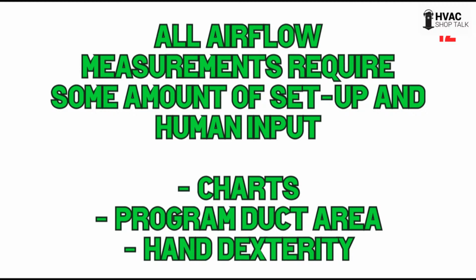Program duct area: all these devices like vane and hot wire, you have to put in what kind of duct you have if you want to calculate the CFM. You don't want to put in the wrong duct, and you want to make sure you measure it correctly, not just say it looks like 12-inch round. You want to measure it correctly because it makes a big difference to what you're getting out. If you give it junk, it's going to give you bigger junk, because every time you measure something, you increase the opportunity that the final measurement you want will be bad.